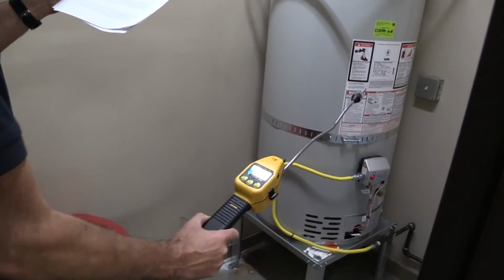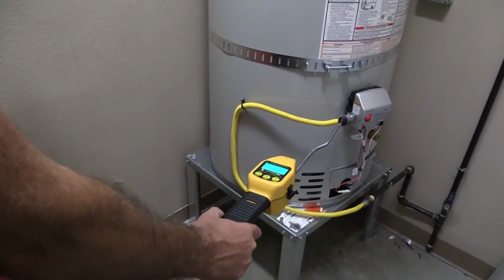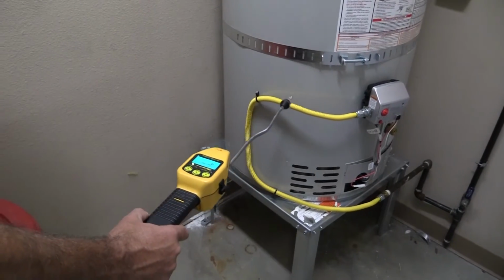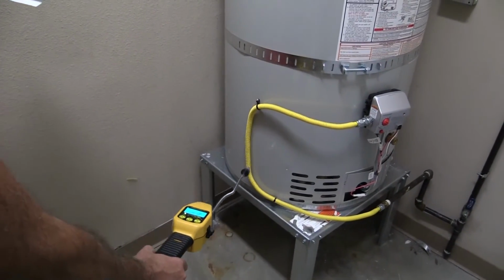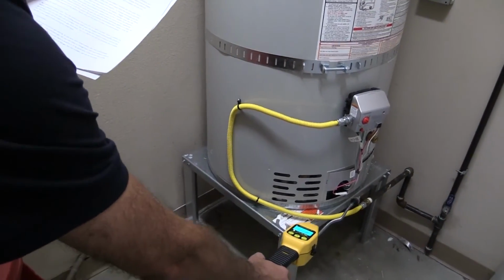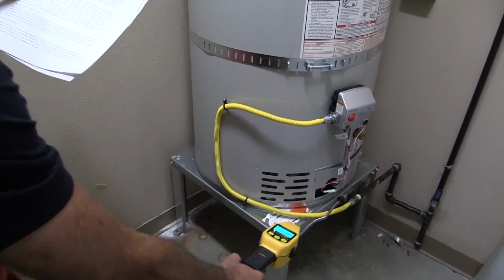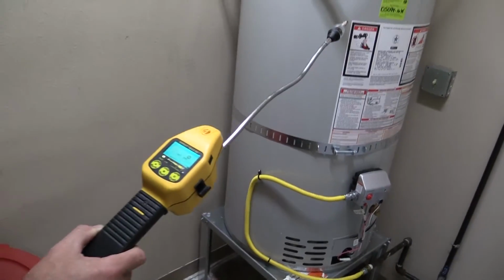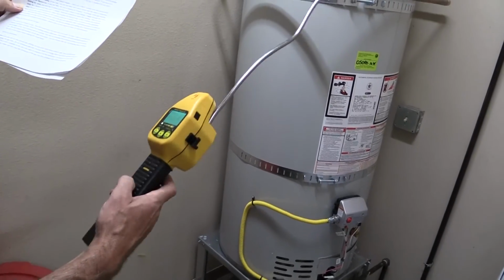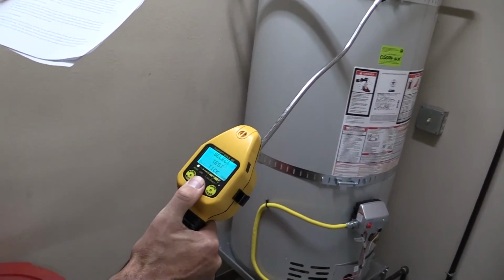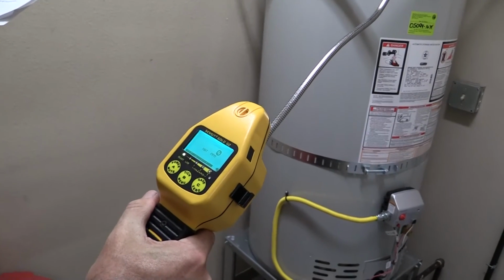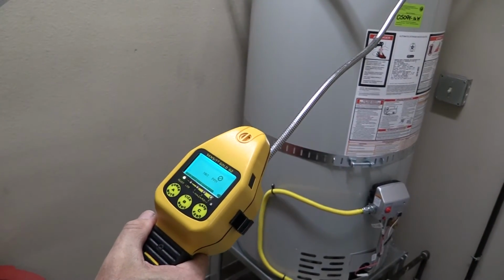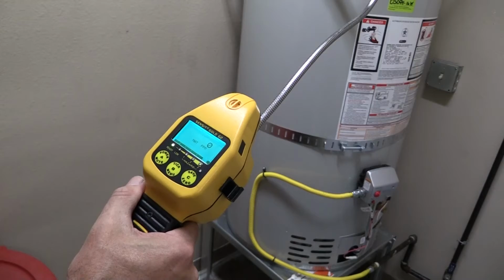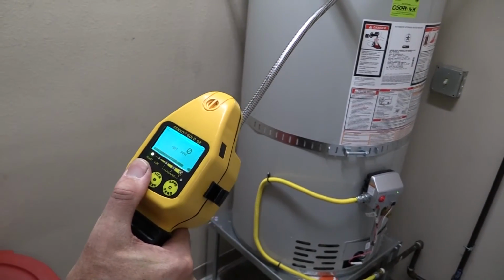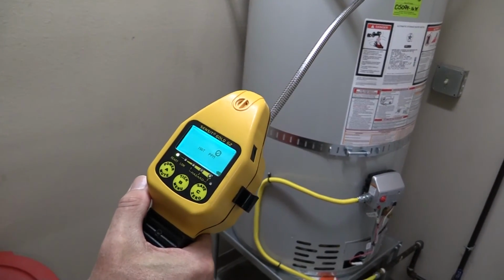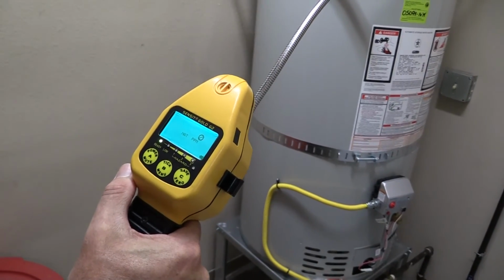Pass the wand over the area that you wish to read. If gas is present, the display numbers will rise. Once the reading passes 2,000 parts per million, the display will automatically switch to a percentage of LEL. You can also use an audible tick rate by pressing the B button twice to turn on the tick. The tick speed will increase as the gas level does. You can silence the tick by pressing the A button. The tick is very useful to use when looking for small leaks.